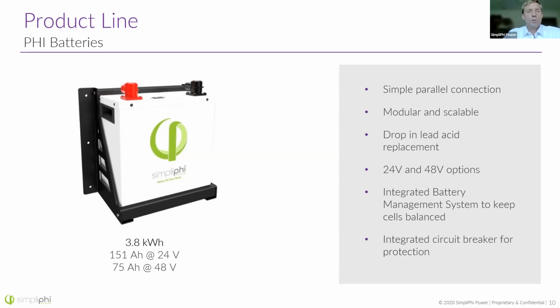These are also designed to be drop-in replacements for lead acid batteries. As many of you have probably experienced, lead acid batteries just don't last. Even under the best conditions, they'll die somewhere around 5 to 6 years in, and often much sooner. So if you have customers with existing solar installations and a lead acid battery bank, these batteries are designed so you can just replace that battery bank.